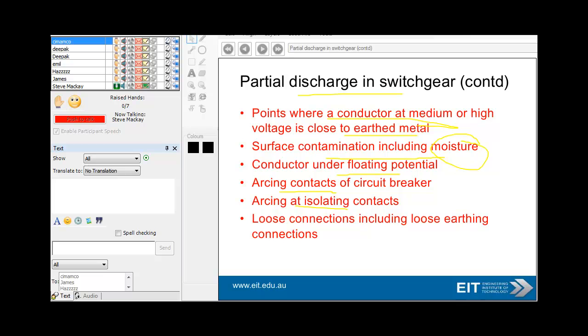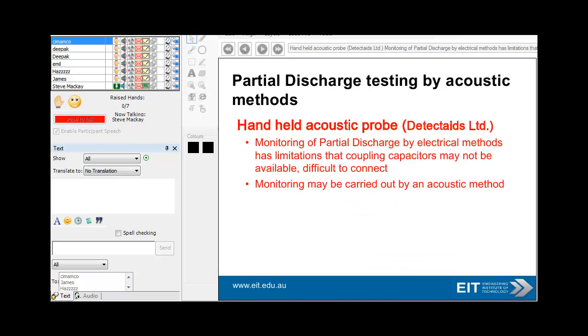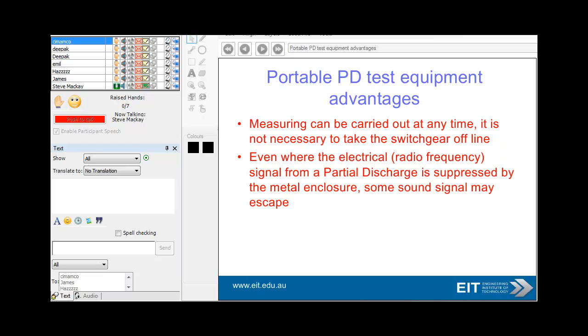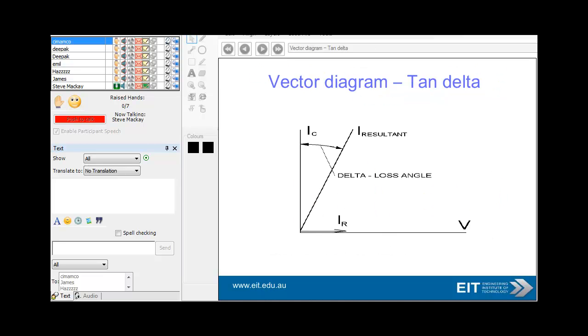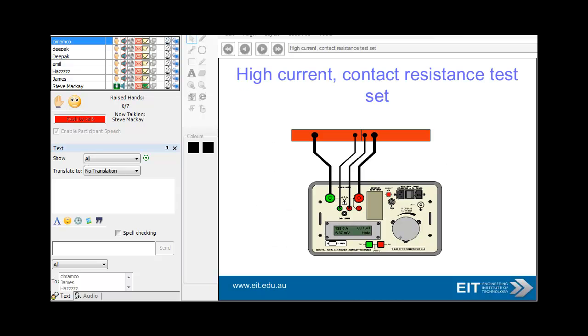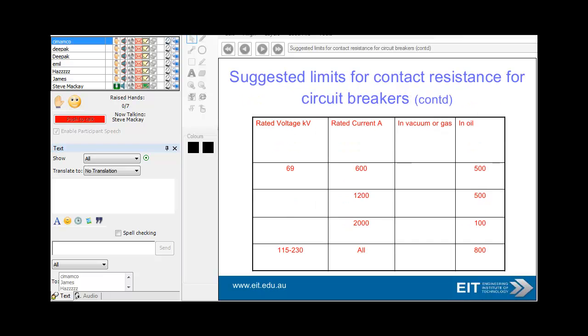Other sources of partial discharge include conductors under floating potential, arcing contacts in circuit breakers, arcing at isolating contacts, and loose connections — which could also present a potential arc-flash hazard. There are handheld acoustic probes available, though you don't need to take the equipment offline to do the testing. There's also a good example of a cracked bushing and its equivalent circuit, which is capacitance and resistors in parallel. Suggested limits for contact resistance for circuit breakers are available in the slides.